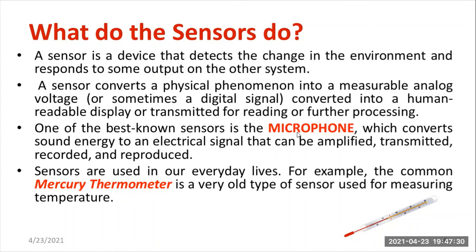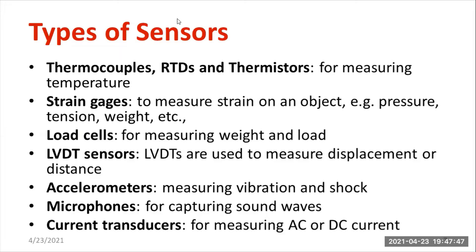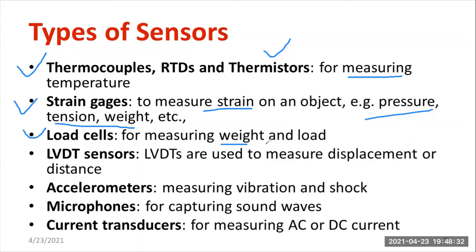Sensors measure changes in physical quantity or the environment — temperature, pressure, etc. Popular examples include microphone and thermometer. Different types of sensors include thermocouples, resistive temperature detectors (RTD), and thermistors. Thermocouples operate on the Seebeck effect: there is a hot junction and a cold junction, and the difference between them produces a voltage. Thermistors are based on positive and negative temperature coefficients of resistance and are used in air conditioning systems. Strain gauges can measure strain, pressure, tension, and weight. For measuring weight and load, load cells are used.